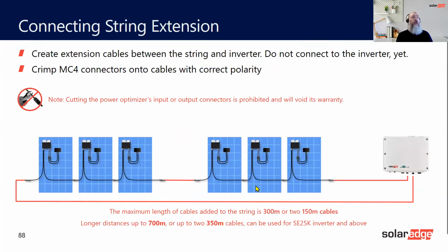And then connecting strings extensions. So with a residential system, you can have up to 150 meters. So from here, it's 150 meters in red, 150 meters in here. So everything in red is up to 300 meters in total, but 150 meters maximum here, 150 meters here. As long as all of it adds up to 300 meters, you don't have a problem.